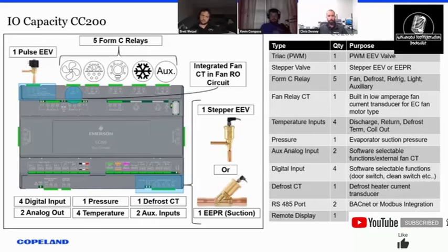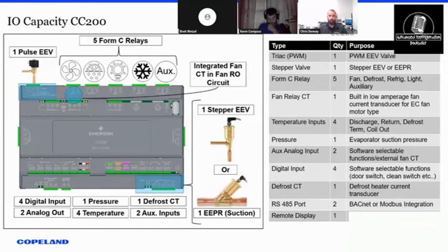Very accurate. It works well. I mean, the defrost heater CT, that thing's killer. If they actually use that the right way, I would save so many in the middle of the night for those calls. Yeah, we're trying to encourage retailers to use that. We have an input for that along the bottom, and we basically generate 2 main alarms based on that. So we'll tell you, hey, the heater was supposed to be on, it didn't come on.